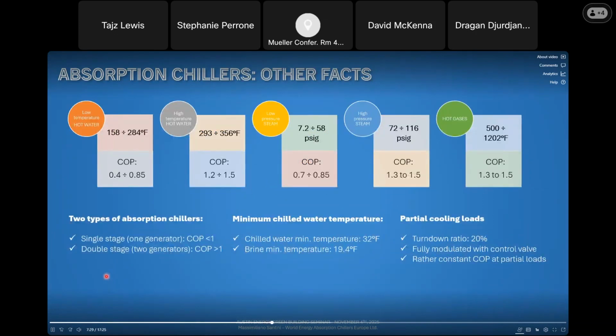There are two types of absorption chillers, single stage and double stage. Single stage chillers work with low temperature heat sources, while double stage chillers need a much higher temperature to work. The difference is also in the efficiency. The COP of single stage units is lower than 1 and greater than 1 for double stage units. The minimum temperature of the chill water that can be achieved is 32 degrees for standard units. For special brine chillers, we can cool the brine down to 19.4 degrees.